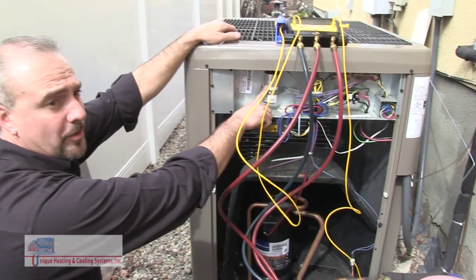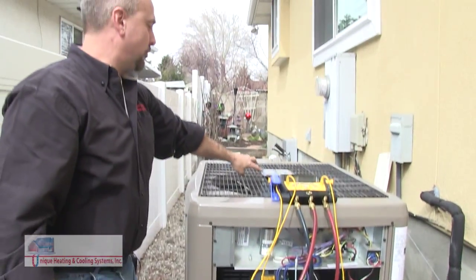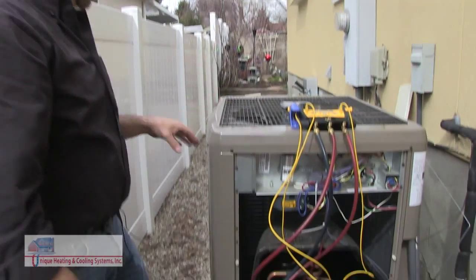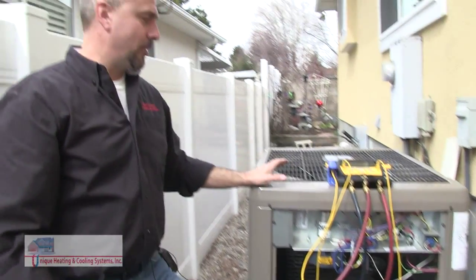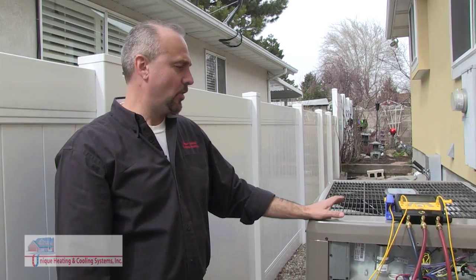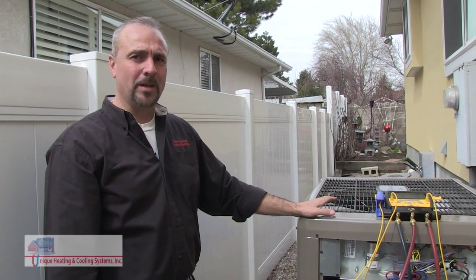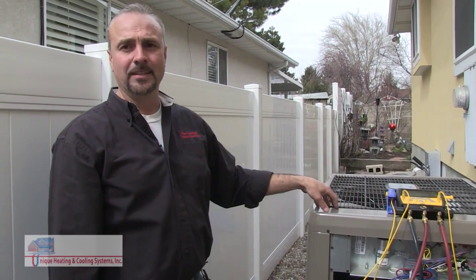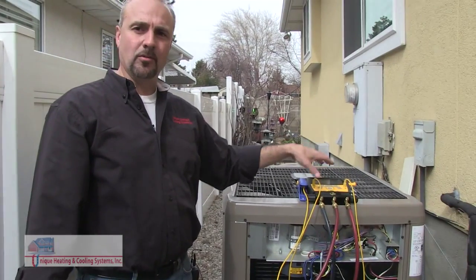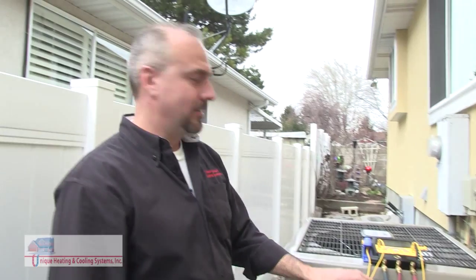3 of the 4 most common service calls that we do on air conditioners relate to either the capacitor failure, the condenser fan failure, or low charge. In fact, a recent Department of Energy study showed that only 32% of all residential air conditioners are charged correctly. That's due to lack of calculation and using the wrong equipment to charge air conditioners. Number 4, and the most common service call on air conditioners, dirty furnace filters.